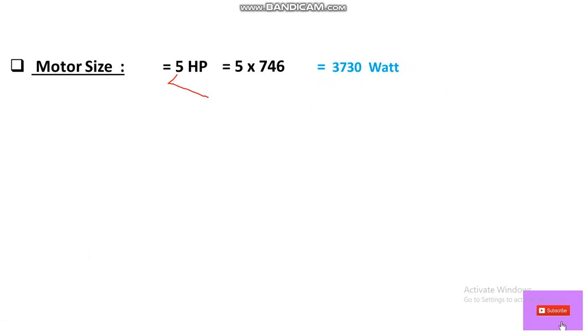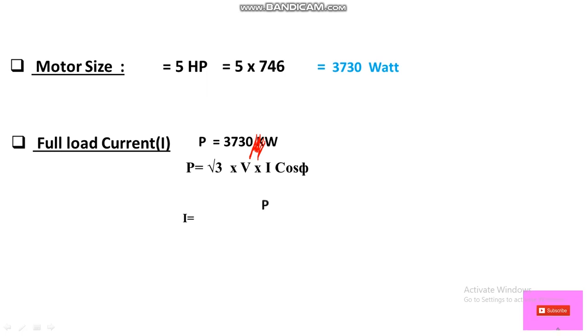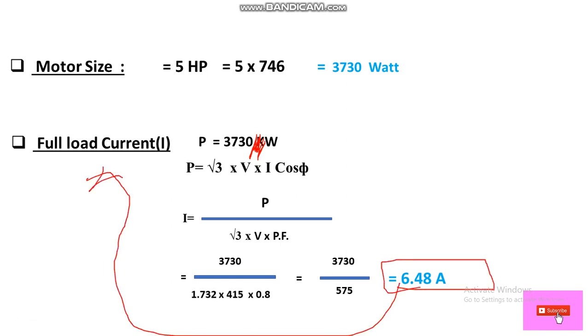Now in step 2, we have to calculate the full load current. The formula for three-phase power is: P = √3 × V × I × cos φ. Rearranging for current: Full Load Current = P ÷ (√3 × V × power factor). Substituting values: 3730 ÷ (1.732 × 415 × 0.8) = 6.48 amperes. So our full load current (FLC) is 6.48 A.